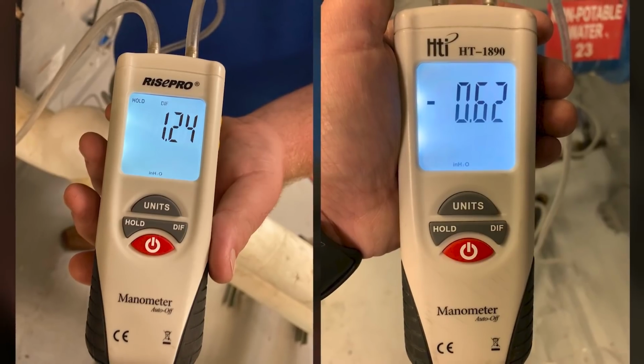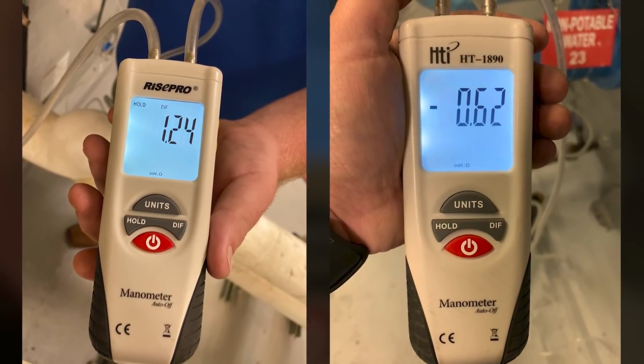Now you might be saying, who cares? So what if the AC has to work a little longer or harder? In HVAC, you measure airflow, and the coil creates what's called a pressure differential. You have a blower, air's coming in. The dirtier that coil is, the greater the restriction, the greater the differential.